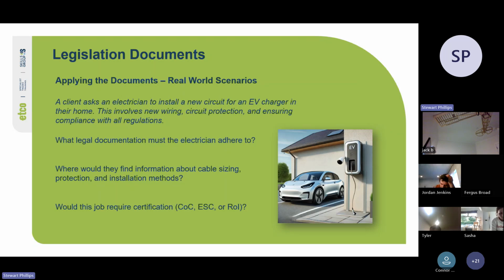So this job would require a COC, a certificate of compliance, for any new installation work. An ESC confirms the installation is safe to connect to a supply. And an ROI, the record of inspection, is not required because this is not classified as high risk electrical work, so an inspector is not needed.